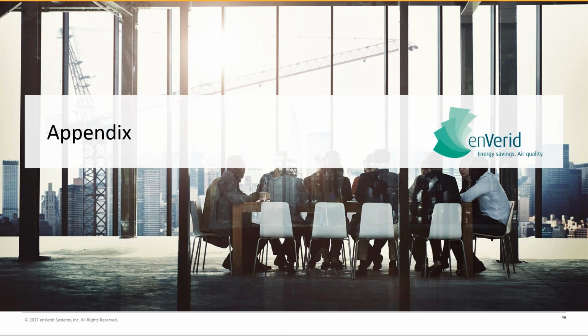Yeah, what a great question. So we love auditoriums, churches, places with highly variable occupancy. And part of the reason behind that is because our units are typically always running, essentially scrubbing air within the space as emissions are released from contaminants that are in the space itself, not just occupancy. So what you end up with there is very clean air from a formaldehyde perspective and some of the other contaminants that you typically see that you might not be reducing as much with perhaps demand control ventilation. And so we're eliminating a lot of those nasty contaminants.